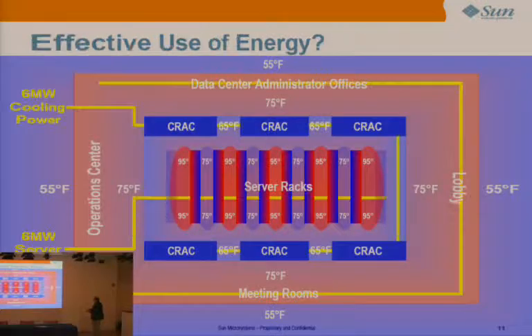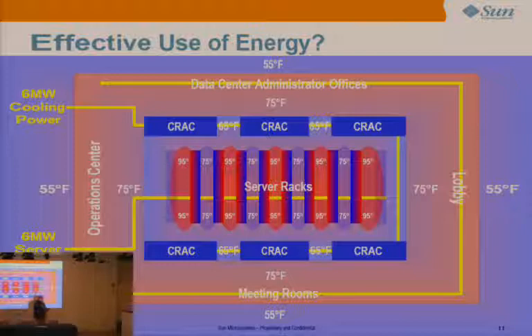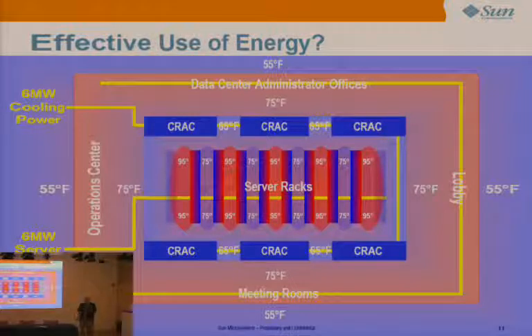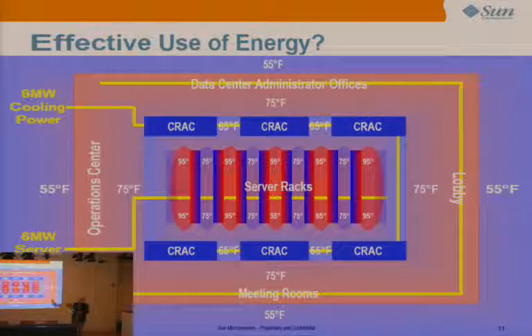So how much power do you need to supply to all of this? In a typical building like this, you might have 6 megawatts of power going to the servers. A typical PUE, a power use efficiency ratio, which calculates the fraction of power that comes into the building that reaches the servers, is typically around 2 or so. What that means is for every 1 watt of energy you spend on the servers for computational reasons, you spend another watt on air conditioning and other overhead.